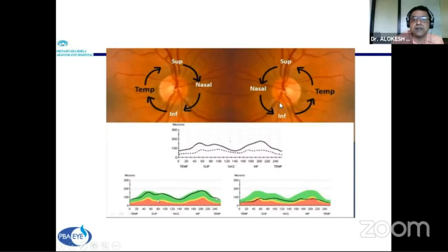So one of the most important things that we must remember is the signal strength value. What is the quality of the OCT that we have performed gives us? That is, a signal strength of 6 indicates a good quality in a time domain OCT. And in a spectral domain OCT, like for example, the Spectralis, a signal strength ratio of about 15 or more gives us the indication of a good quality of a scan performed.